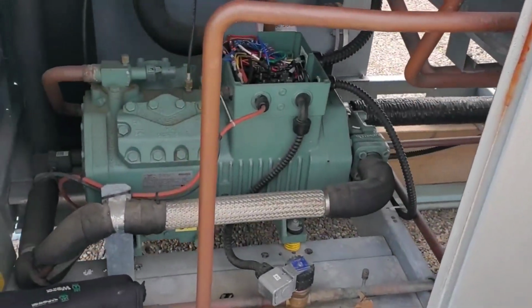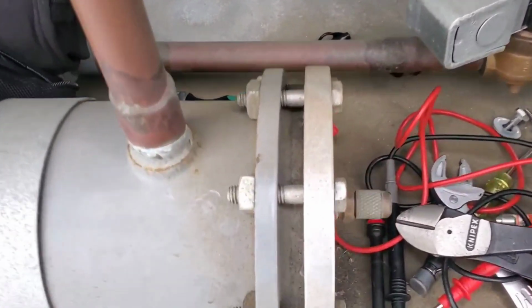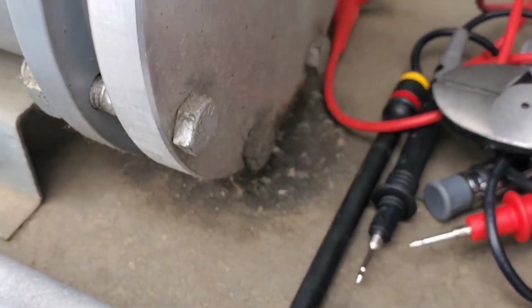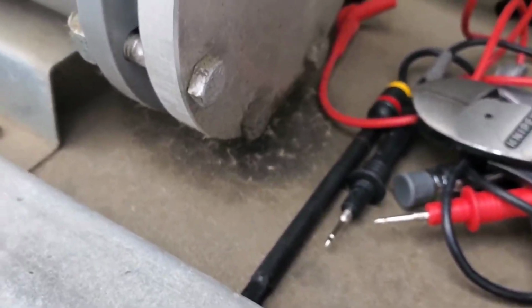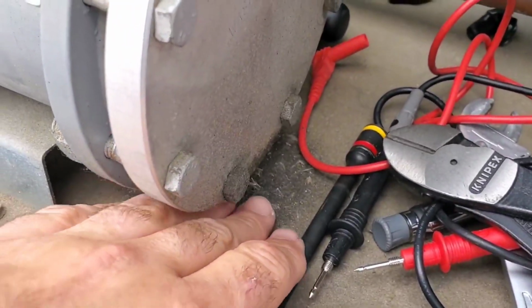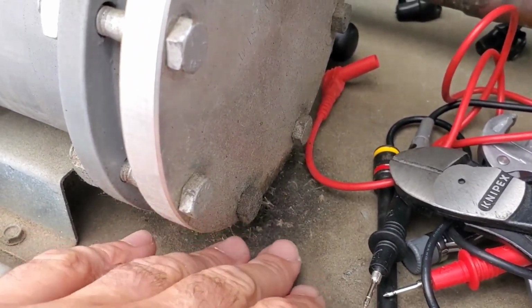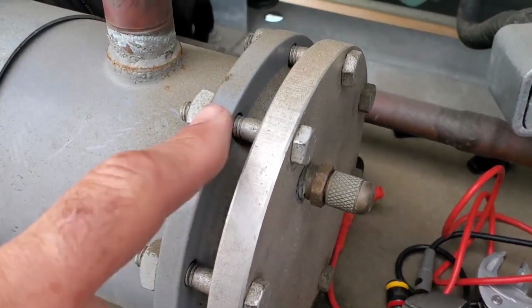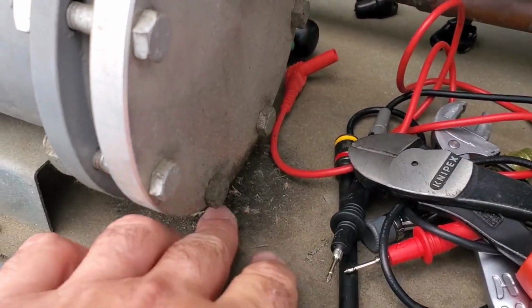There's one other thing I'm gonna check here, and that is a potential sign of a leak with this oil right here. There's an oil stain right here. I got my leak detector, and I'm gonna check this flange plate here to see if there's any leak from this filter dryer. Okay, so that was leak check. There was no leaks there. I don't know where the oil came from. Maybe it was a leak at some point in time, but it's not leaking now, I can assure you that.